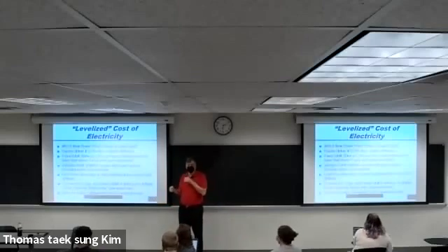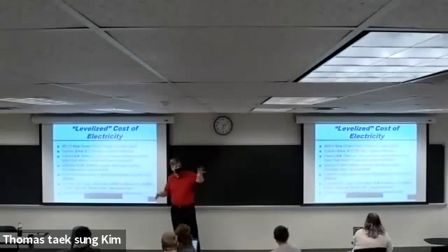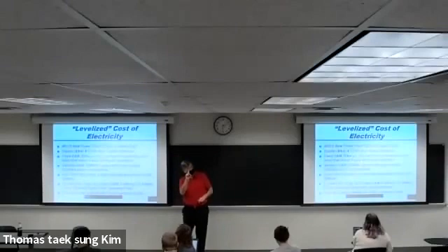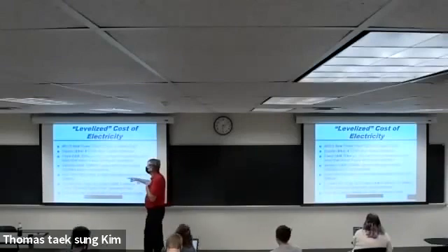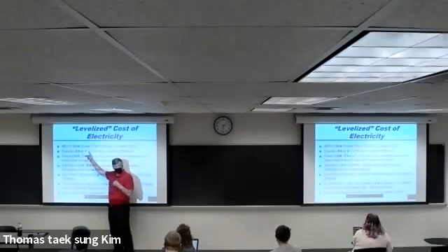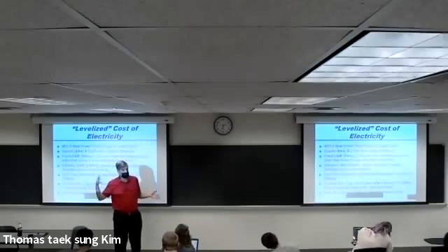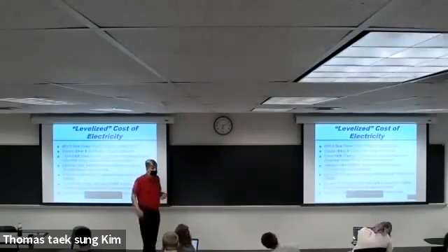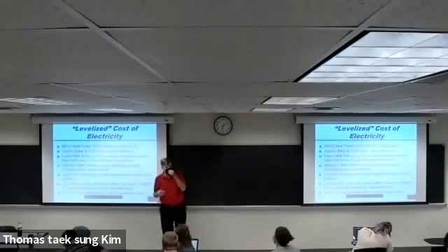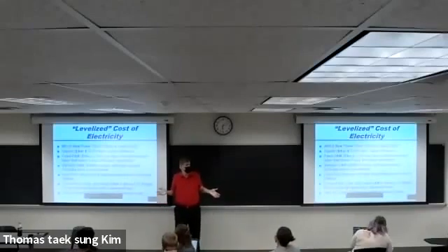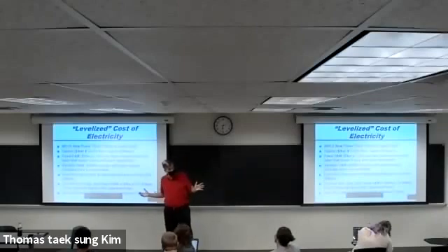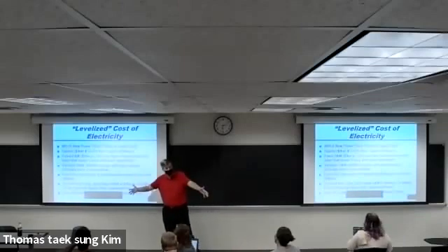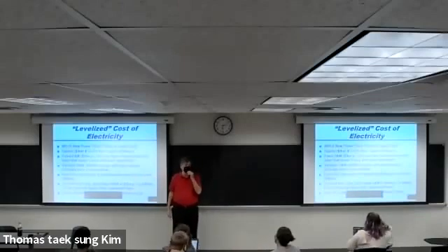So one part of the levelization factor is just depreciation, right? Over 20 years, 5% a year, right? Well, that's part of the capital charge rate. But then there's also things like, well, you pay interest, you borrow money, so you pay interest on that. You might pay 3 or 4% a year of interest on a declining basis. So when you add up all those things, there might be things like taxes included in the levelization factor, right? You might pay property tax, you probably do, for the land you're using for that power plant. And that often gets included in the capital charge rate.